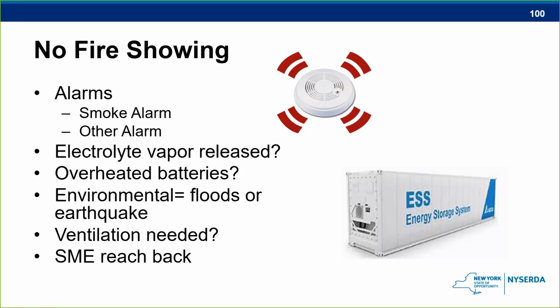So what New York City decided to do is to try to have some sort of ventilation for the firefighters to release those gases so they wouldn't put their forces right next to the actual enclosure itself. So that fan would actually pull those gases out. Would it stop an explosion? It may not stop an explosion, but the firefighters could still be a distance away when they turn that exhaust fan on to pull that stuff out. So that would be a remote turn-on switch for them to use, and they would pull the gases out of there.